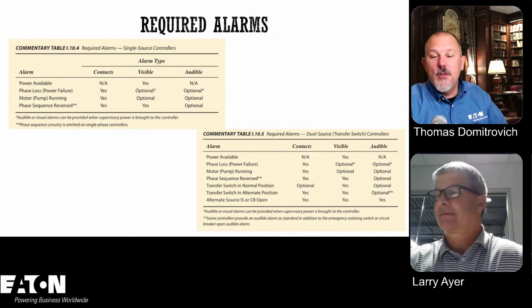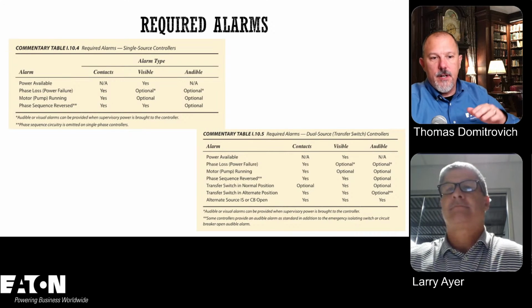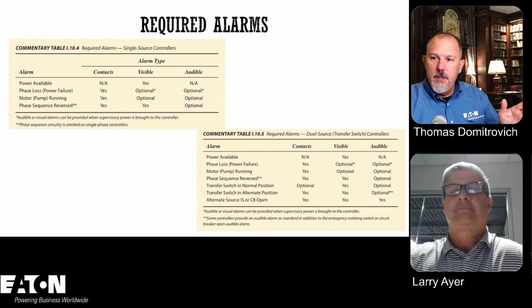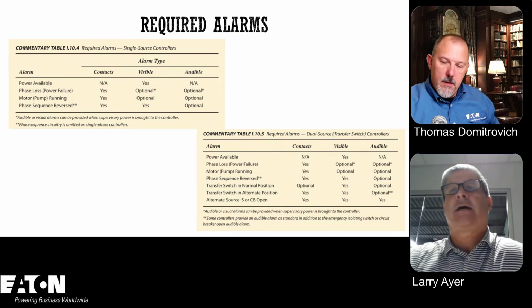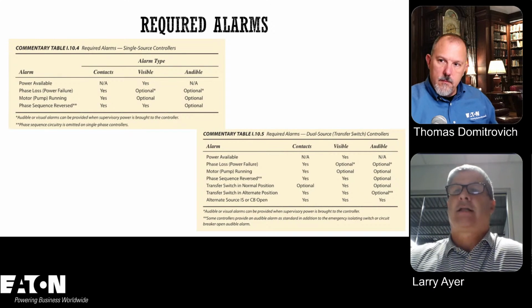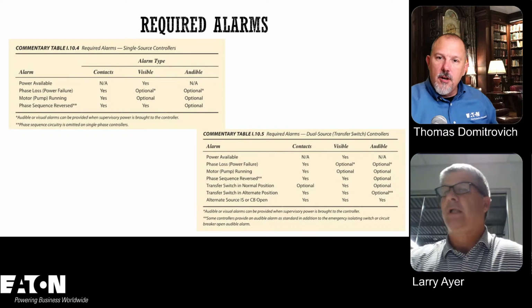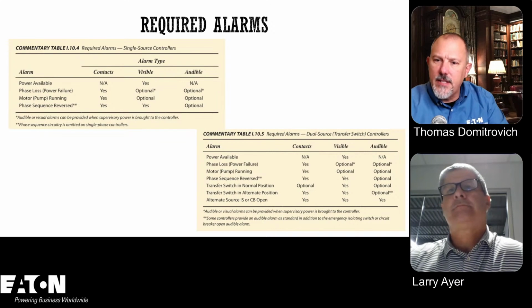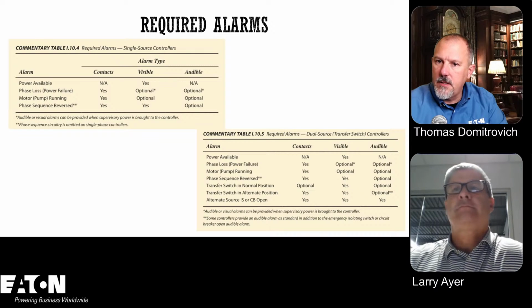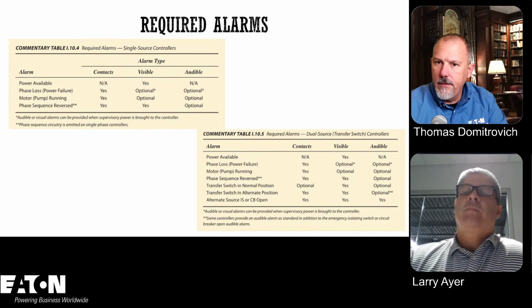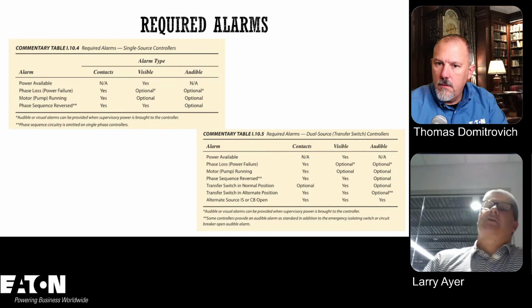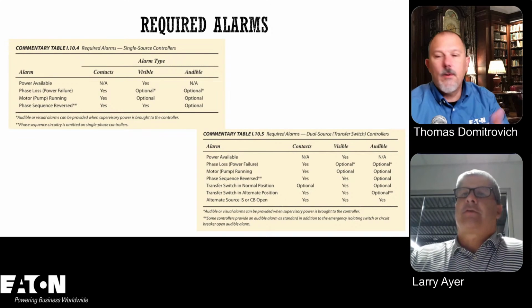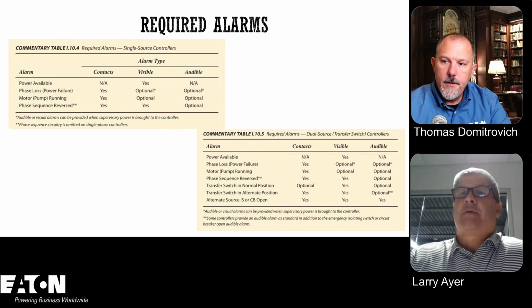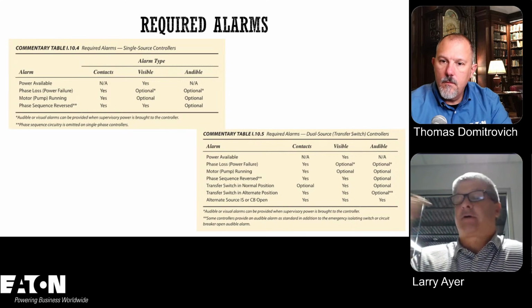Okay, so required alarms. So alarms, and you mentioned this earlier about 72, right? NFPA 72. And well, this is actually in NFPA 20. Yeah, but there's alarming requirements. Is there a 72 angle here at all with regard to pulling off the alarms from the fire pump system, or no? Well, I think that NFPA 20 tells you the alarms that you have to provide for the fire alarm system to be able to notify someone. So you're going to basically tie these into the fire alarm system.